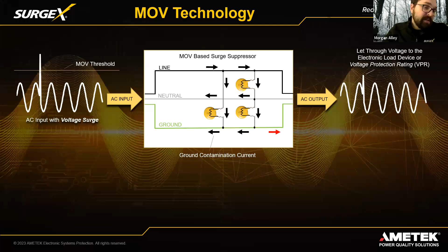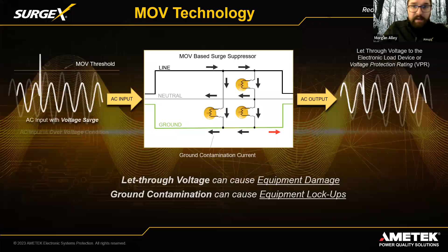The next thing to really think about, that I spoke about earlier, is our surge elimination versus MOVs, which have a substantial amount of let-through voltage. So if you look at the two sine waves, the input and the output, obviously the spike, once it's gone through an MOV, has been greatly diminished, but there's still a spike in that sine wave. We call that let-through voltage. So even though it's dissipated and diverted energy, it's still letting a sometimes substantial amount of let-through voltage through, whereas our reactor core does not allow let-through voltage. Again, up to 6,000 volts. But if you have a more than 6,000 volt problem, your wiring is probably on fire and you've got bigger fish to fry.